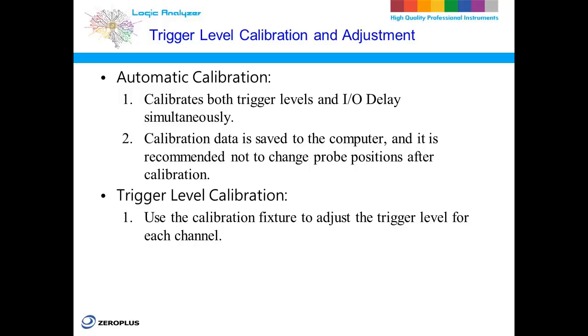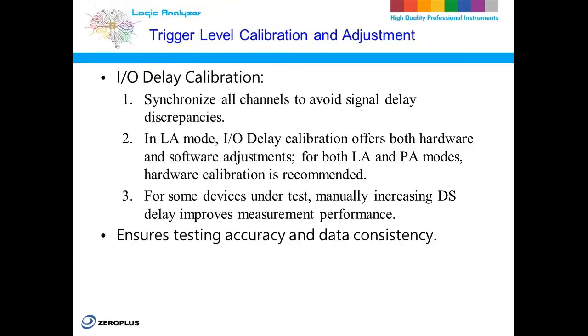For trigger level calibration, we need to use a special calibration jig. This ensures that the trigger level for each channel is accurate. I/O delay calibration. I/O delay calibration is mainly used to synchronize delays between different channels to prevent any signal delay mismatches from affecting the measurement results.